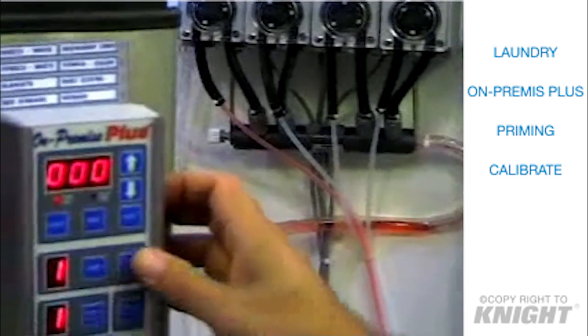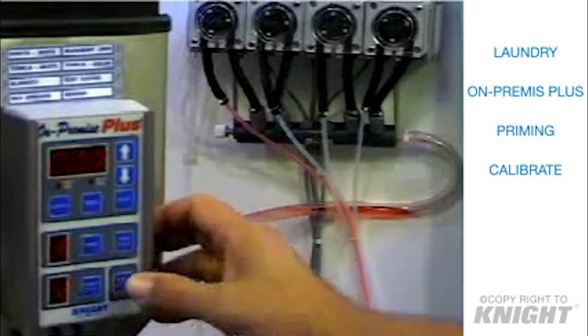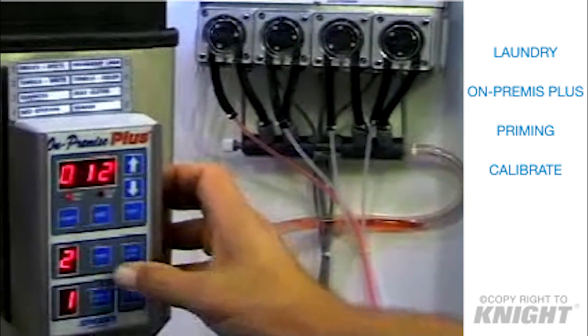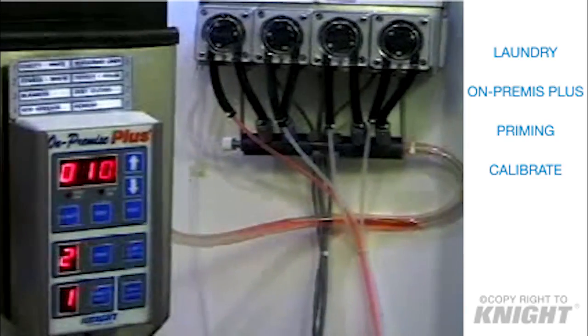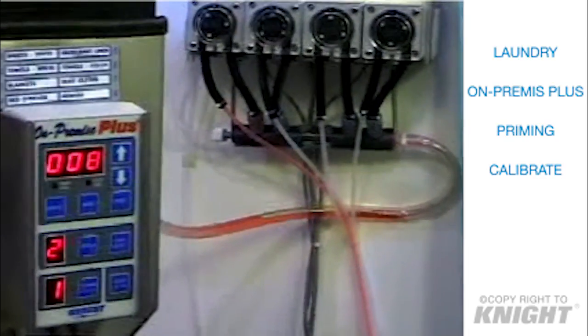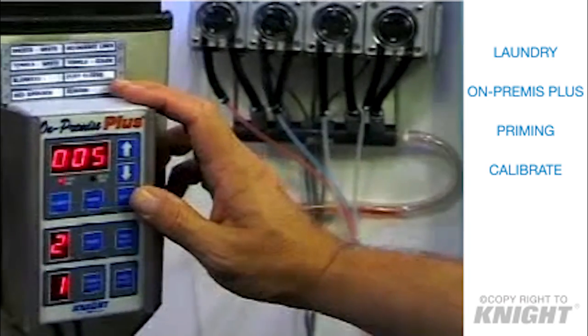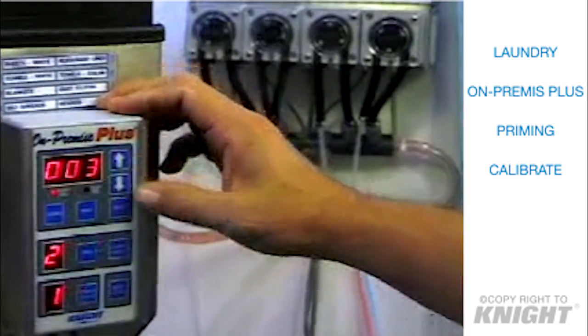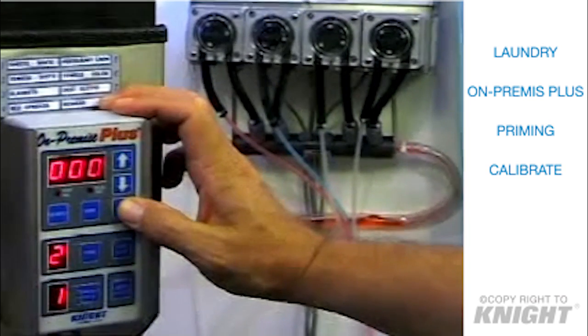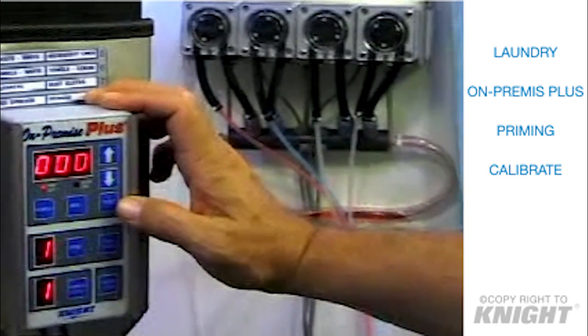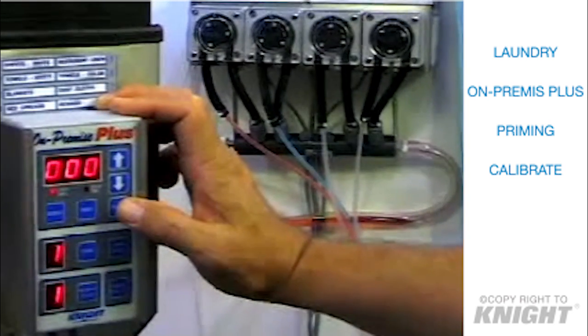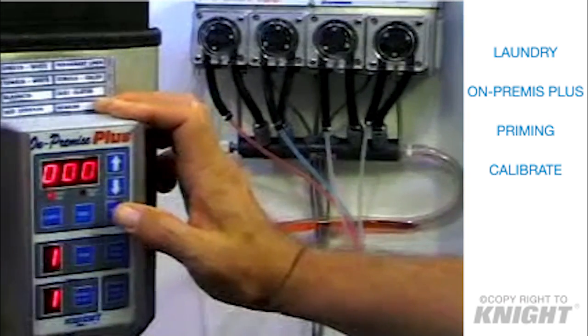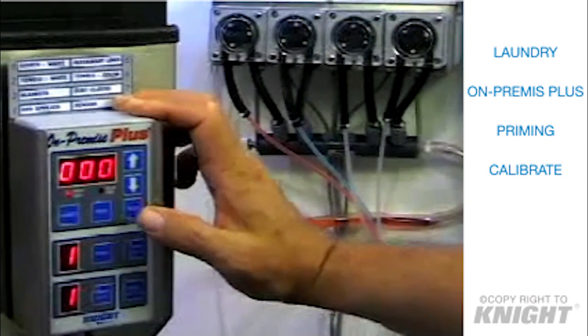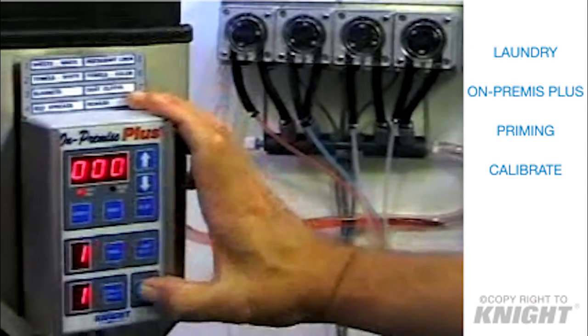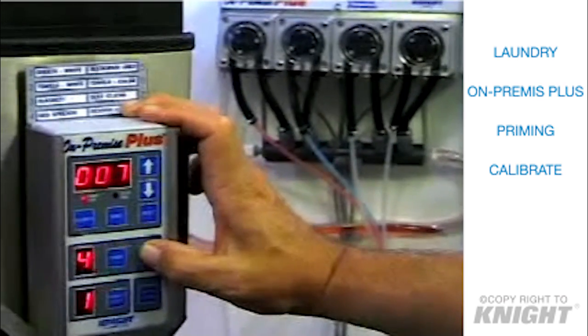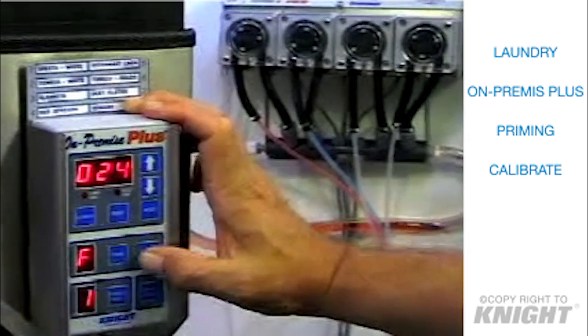I select my second pump. Again, I have to get access. Hit the prime button again, and you'll see that pump number 2 will prime. I can either let it count down to 0 or I can hit reset to stop it. Let's go ahead and stop it. And repeat that procedure for each of the pumps on your system, including flush. If you want to prime flush, simply get access again, select F for flush, hit prime.